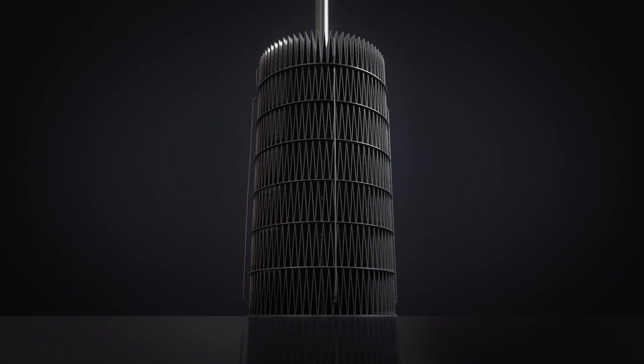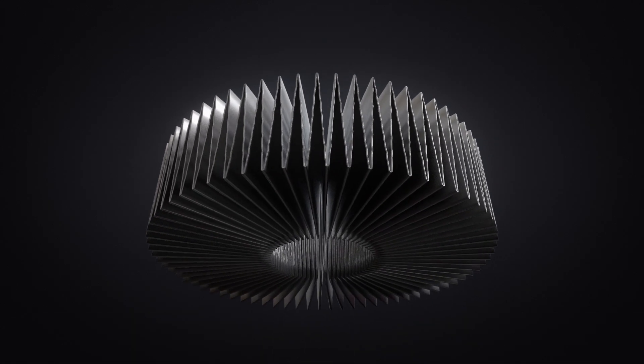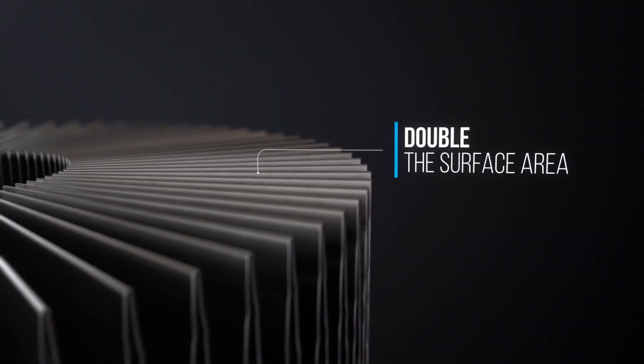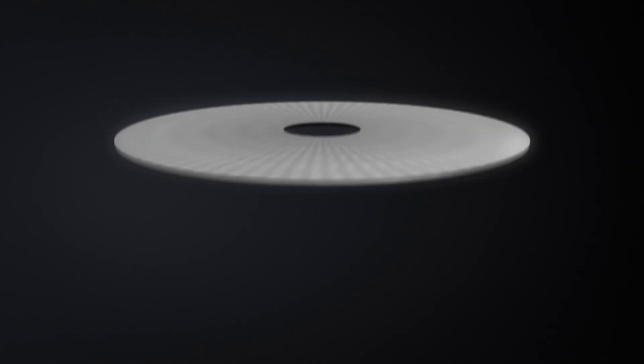Its uniquely engineered structure is made of catalyst coated foil supports, or fans. These fans offer up to double the surface area compared with pelleted catalysts. The SSR is manufactured to address your reformer's unique limitations and demands.